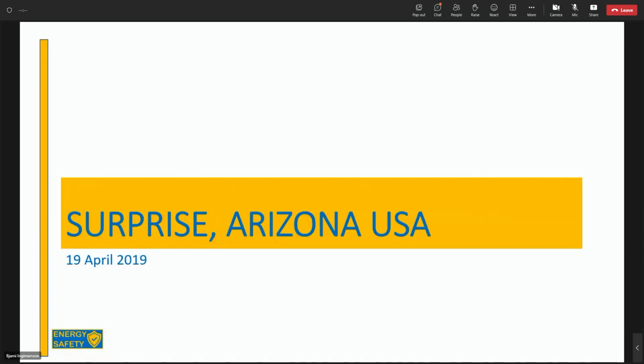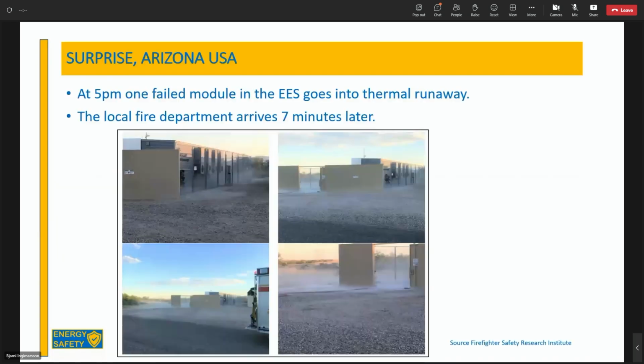This was another incident, in Arizona. At 5 p.m., one failed module in the energy storage system went into thermal runaway. The local fire department arrived seven minutes later and saw smoke, but no one knew what it was, because no one had told them there was an energy storage system at the site. This is already the case in a lot of incidents: firefighters don't know, and they have to give advice about something they know nothing about.